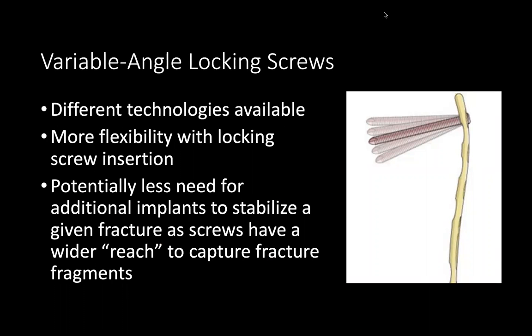Variable angle locking is a newer technology — within the last 15 years — where you can still lock screws into plates at a variable angle rather than a strict 90 degrees. Plates may allow 10-30 or even 40 degrees of variable angle. This provides more flexibility when placing locking screws around joints or fracture sites, allowing you to angle away from certain structures. Companies commonly use this as a selling point, comparing their variable angle ranges.